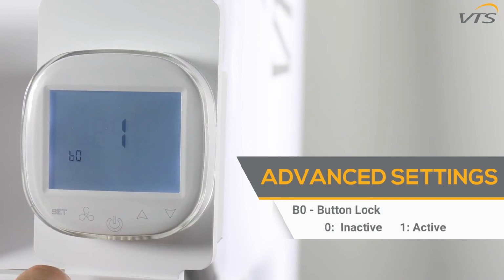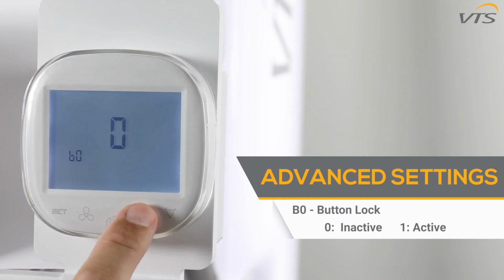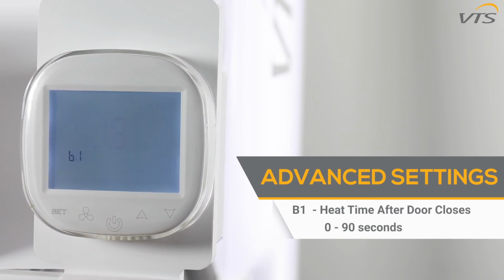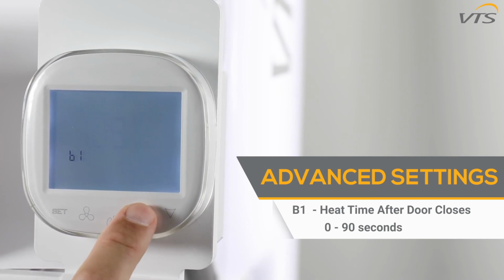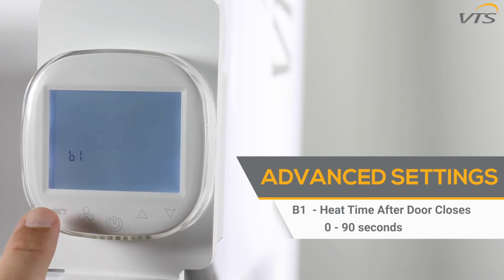The B0 function gives you the option to lock the controller. 0 makes it impossible to lock the controller, while 1 gives you the ability to lock the controller. The B1 function allows you to set the amount of time the curtain will keep heating the room after the door is closed. You can set it from 0 to 90 seconds.